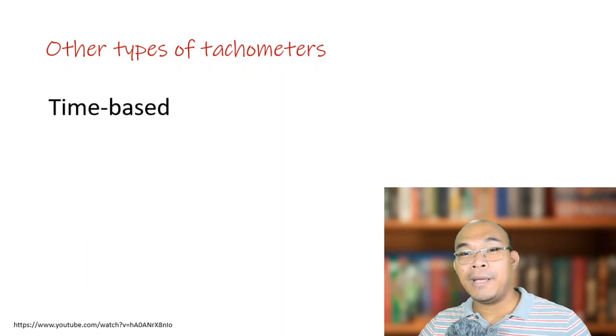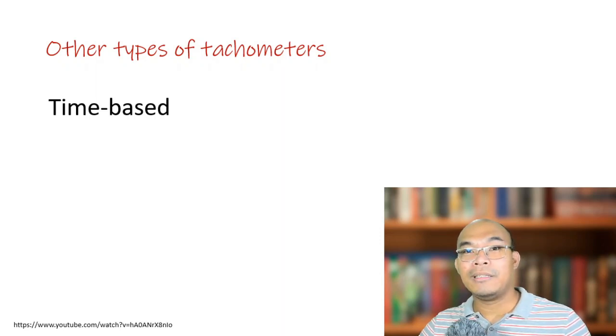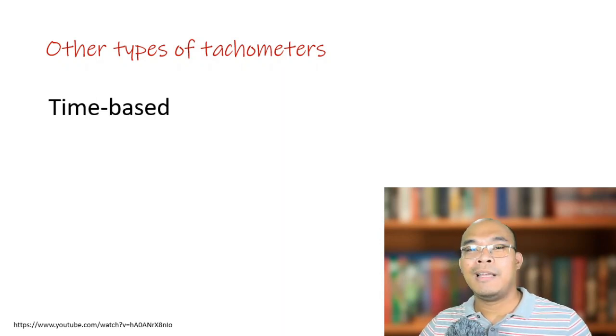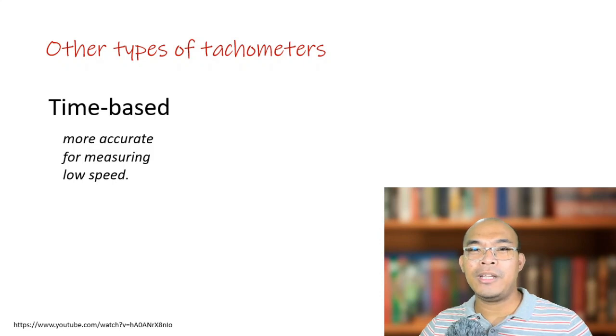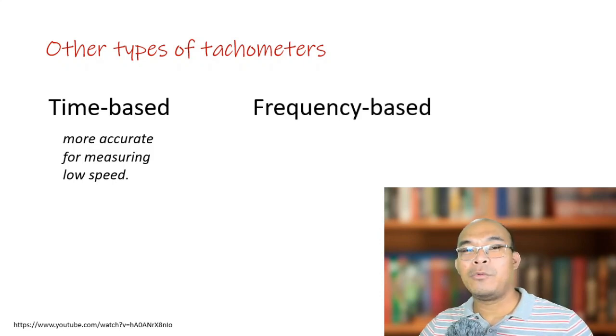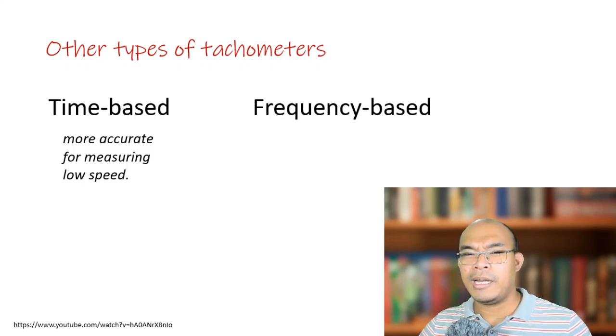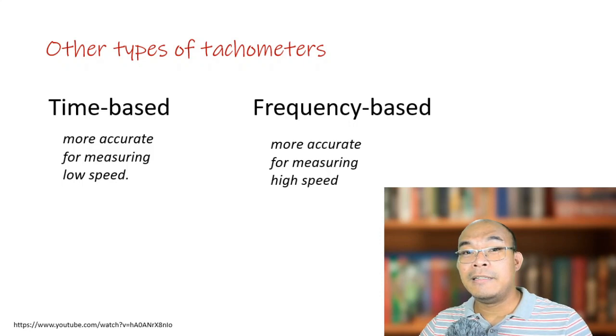The last types are time-based and frequency-based digital tachometers. A time-based digital tachometer calculates speed by measuring the time interval between incoming pulses; this type is more accurate for measuring low speed. A frequency-based digital tachometer calculates speed by measuring the frequency of the pulses; it is designed using a red LED, its revolution depends on the rotating shaft, and it is more accurate for measuring high speed.